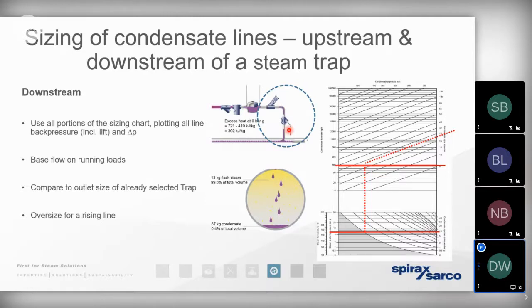If we don't do that, then that huge increase in volume is going to place a huge back pressure on the steam trap itself. And that's going to hold back the condensate and start to flood the process. It means that huge expansion is going to energize the condensate in the pipework very, very quickly. It's going to push that condensate with a lot of energy, creating water hammer and violence. And ultimately, the flash steam is going to be vented away to atmosphere at the nearest vent.